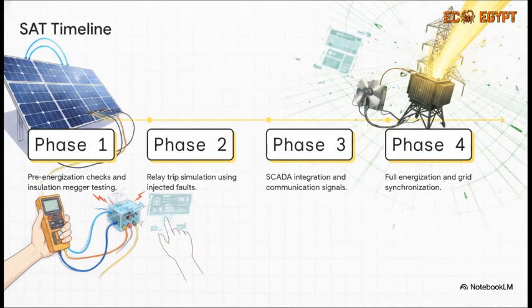Fast forward to the site, and the SAT follows this completely unforgiving timeline, from rigorously checking the insulation resistance with Megger testing, to simulating relay trips, to finally verifying all those SCADA data links are actually live. This strict sequence forces the team to prove the plant's protection logic works flawlessly, because with one single mistake, or one bypass step here, live grid power could literally destroy the entire system the exact second they flip the switch.